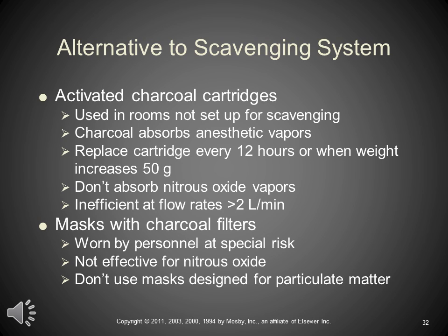The alternative to scavenging systems are the activated charcoal cartridges, which we see very frequently. These are used in rooms not set up for scavenging. The activated charcoal will absorb the anesthetic vapors, and you may be familiar with these. Your practice may be using them. You need to replace the cartridge every 12 hours or when the weight increases 50 grams. They don't absorb nitrous oxide vapors, which is not a big deal because nobody uses nitrous oxide anymore. And it is inefficient at flow rates greater than 2 liters per minute.